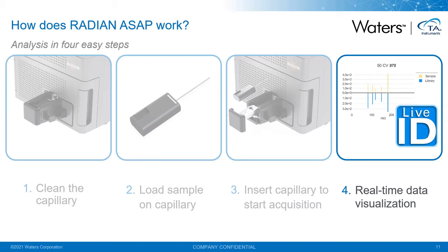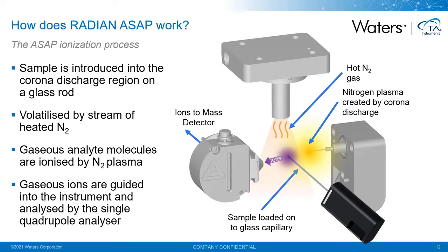That's the basic workflow of analysis using Radian ASAP. The source geometry should be very familiar to those with prior knowledge of mass spec techniques. The sample is introduced into the source on a disposable glass capillary from the front of the instrument. A stream of heated nitrogen gas serves two purposes: it provides heat to the glass capillary to volatilize the sample, and it creates a nitrogen plasma in the region around the corona discharge pin, which is the basis of the predominant ionization mechanism. The nitrogen plasma indirectly creates ions from volatilized molecules, which are guided into the instrument and sorted by mass-to-charge ratio before being detected to generate the mass spectrum.